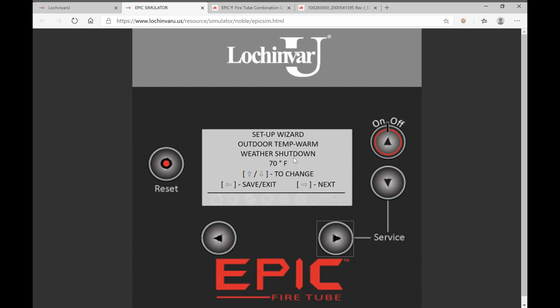Moving along, our outdoor shutdown. At what point outside is our boiler just going to stop running and not produce any heat, based on the temperature outside? The factory sets a default of 70. Again, this can be changed. Then we go into our automatic reset high limit. If we hit 200 degrees, our boiler is going to go into a high limit error code, and then it will reset by itself once the temperature lowers. This again is adjustable.